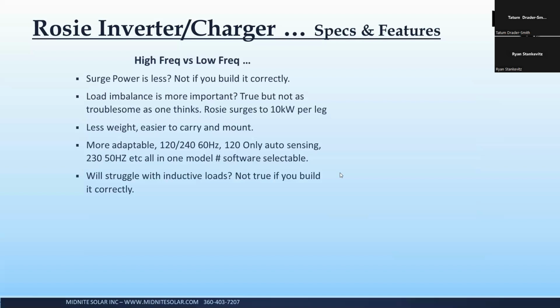But depending on your ambient temperature and everything else, at 21 kilowatts, you're probably going to get about 2 to 3, 4 seconds. At maybe 15 kilowatts, you're probably going to get almost the full 5 minutes. So it's just going to depend on the amount of surge, the length of the surge, and the ambient temperature. But the fun part is, like I said, one of my jobs was to sit down and say, okay, what does all of our competition do? I started making a spreadsheet so I could try to compare surge power over time, and every inverter I found used different times and different numbers to make it work.